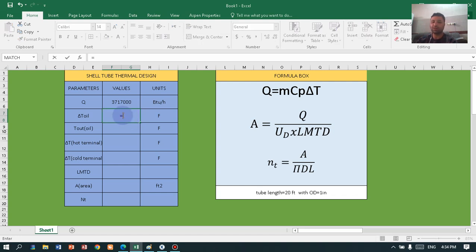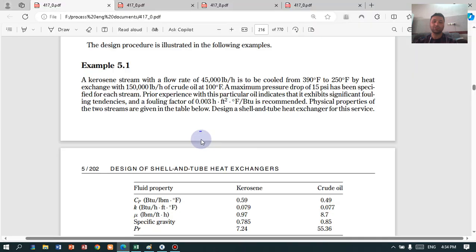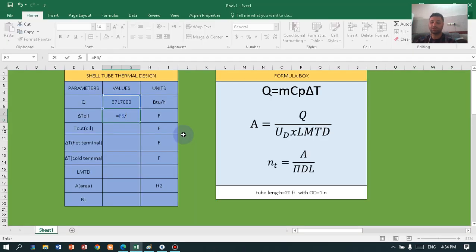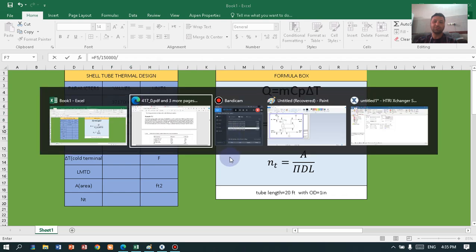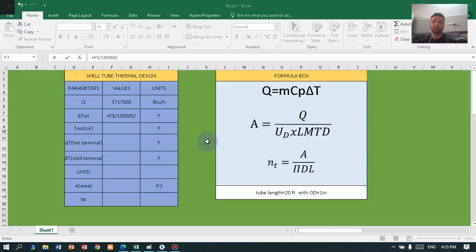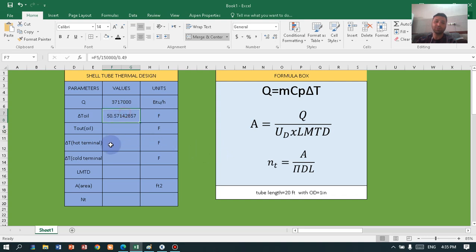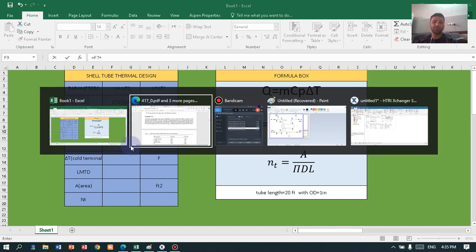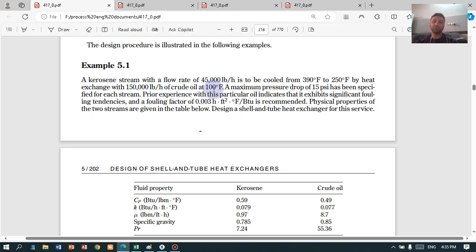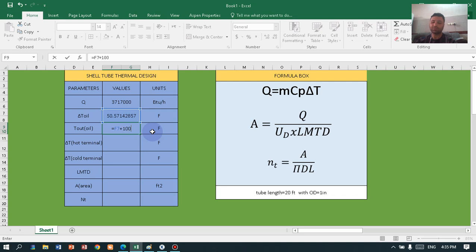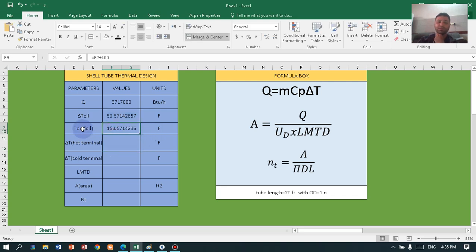Now let's calculate the differential temperature on the oil side, which is on the tube side. Take the heat load and divide by the mass flow rate on the tube side, which is 150,000, then divide by the heat capacity for the oil, which is 0.49. Press enter and we have the differential temperature. For the outlet temperature, add this number to 100°F at the inlet of the shell and tube, giving us the outlet temperature of the tubes.